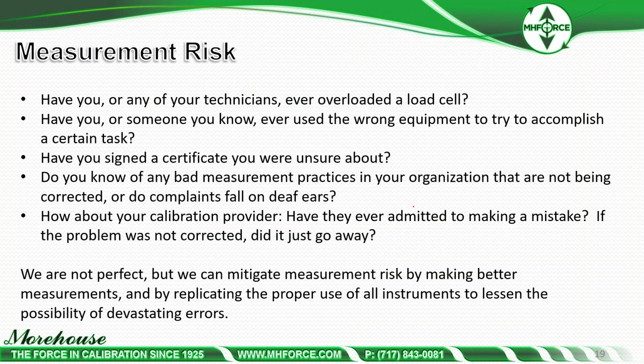So questions for people, generally: have you or any of your technicians ever overloaded a load cell? This happens frequently. It's not horrible. It should be a learning lesson. There are some things that you can do. If you're at constant risk for overloading load cells, you can buy load cells with higher capacities. For example, if you wanted a 2,000-pound load cell, but you thought your techs were going to overload it, you might consider using a 5,000-pound load cell and just derating it to 2,000 pounds. Overload or permanent shift would happen at 7,500 pounds in that scenario as opposed to 3,000.